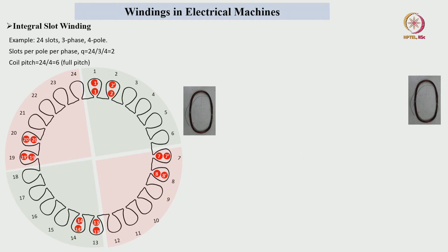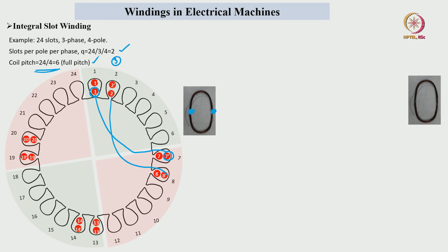Integral slot winding means slots per pole per phase gives an integer — 2, 3, or any integer. Whether it is full pitch or short pitch, we make the coil pitch accordingly and place coil sides as per the winding diagram. For full pitch double layer winding, the first coil side is placed in slot 1 top side and the second coil side in slot 7 bottom side. Then 2 to 8-dash, 7 to 13-dash, 8 to 14-dash, and so on. Winding diagrams will be discussed in detail in coming lectures.